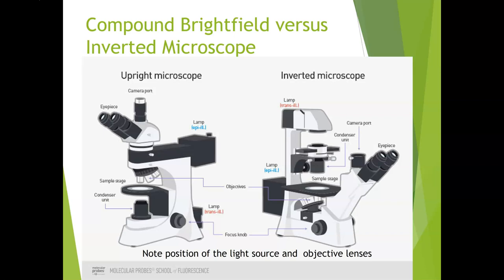This image compares the normal laboratory microscope — the compound brightfield — with the inverted phase contrast microscope. In the upright brightfield, the objective lenses are above the specimen on the stage, and the light source and condenser are below the specimen on the stage. The inverted scope has the light source and condenser located above the stage, and the objective lenses are below the stage. These differences are key to the different applications: the upright brightfield is used for stained slides, but the inverted is used for living cells in vessels placed on the stage.